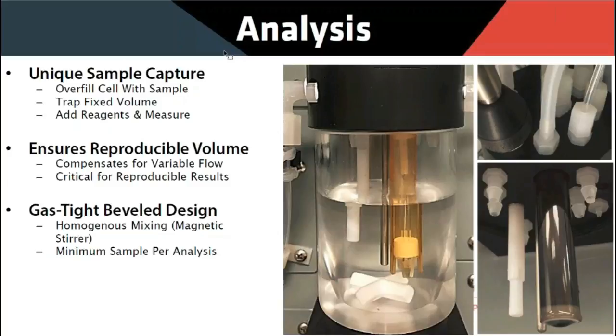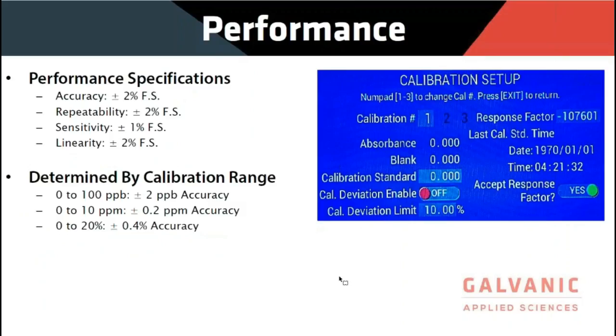And we also have homogeneous mixing via the magnetic stir. Performance is all between 1 and 2% full scale. When a customer is deciding what calibration range they want, they need to think about where they need the greatest accuracy. If they want the full scale of 10 ppm, but it's very critical at 100 ppb, obviously we want to calibrate at a lower range so that there's greater resolution there. Here we have a few examples of, based on the range, what the accuracy would be.